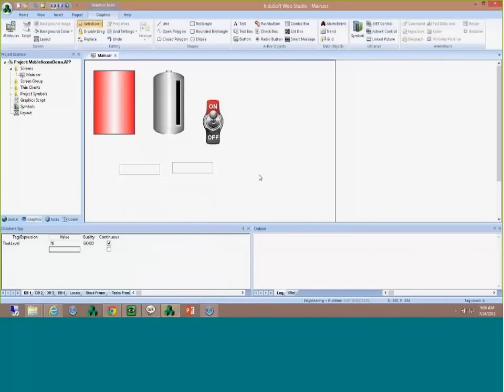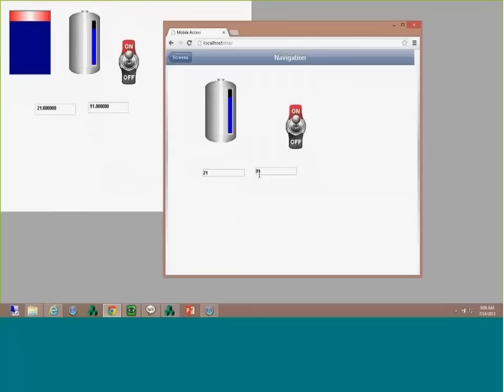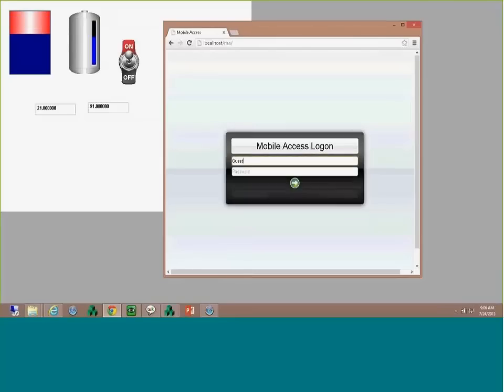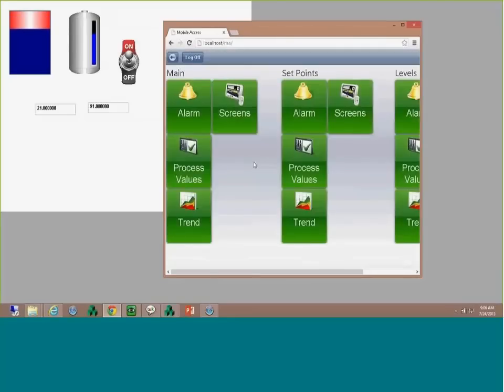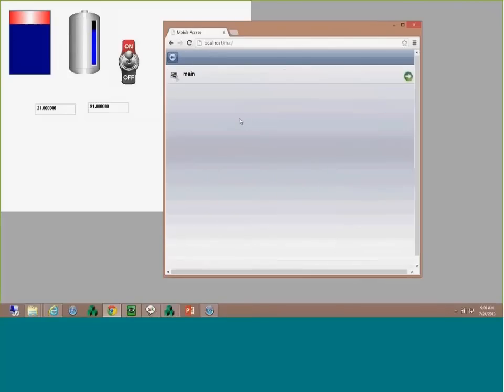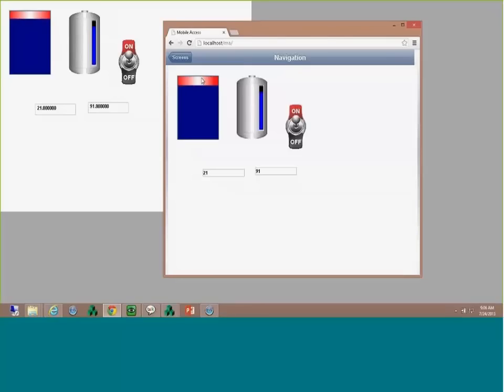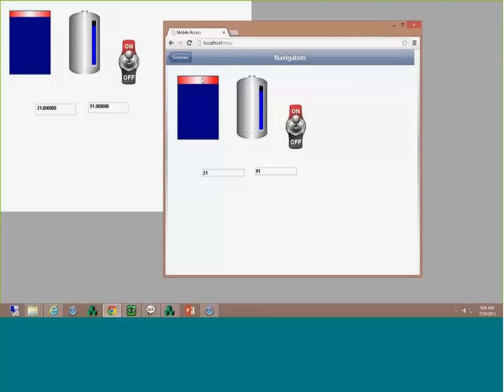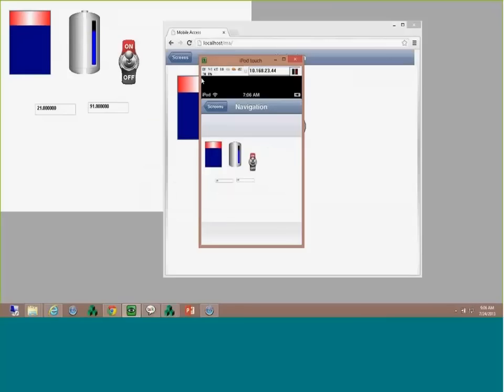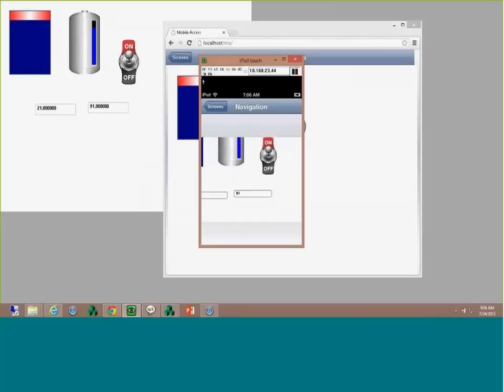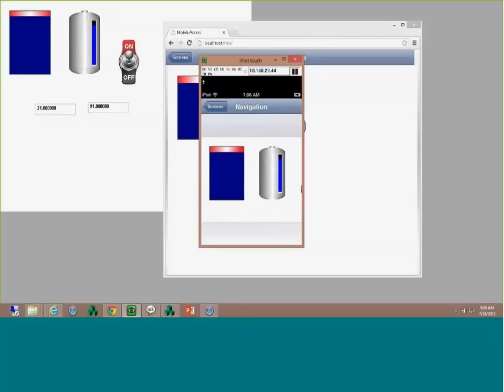I'm going to add an ellipse and change its color to demonstrate color animations. I'll create a gradient: if the tank level is 0 it'll be one color, if it's 20 it'll be green since that's a good level, and above 80 I'll make it red. I'll save it. On the Indusoft runtime the ellipse is red because the value is 91. As the value changes, the color changes. Going back to the web interface in Chrome, you can see the ellipse changing colors. On the phone, zooming in, you can see the colors changing as well.